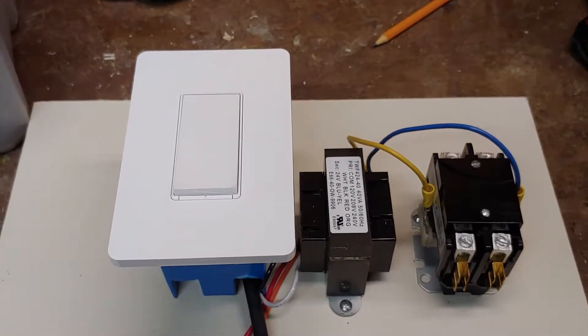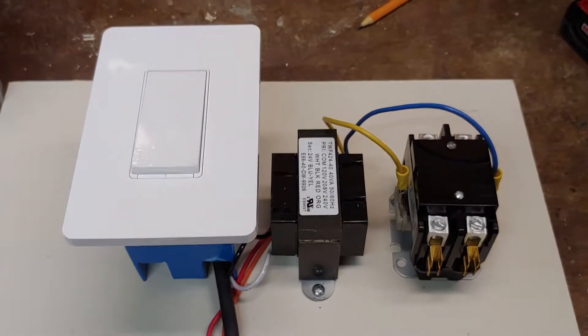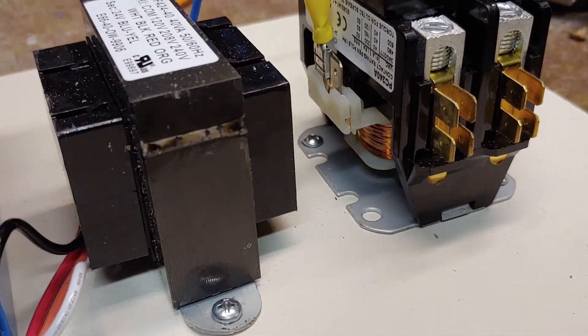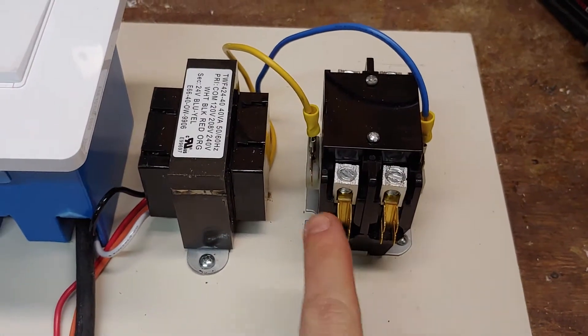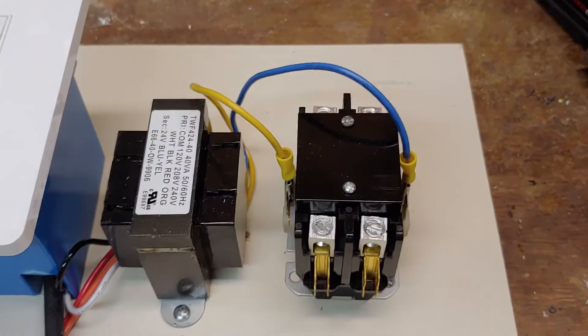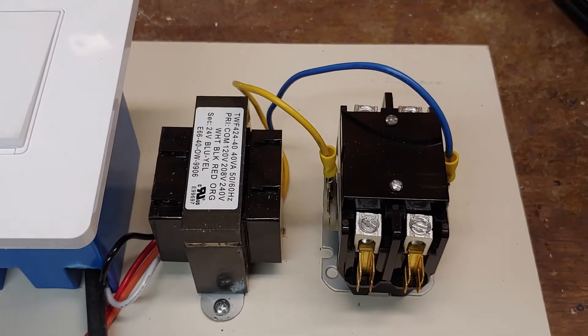So that you can control a high amperage or high load device, you can use a contactor. The contactor has a 24 volt solenoid in the bottom of it, and you can run 240 volts. You've got one hot, one hot, and it's switched to these two. You take the same hot over here, and it will switch them on and off. It's a nice relay, and it runs off a 24 volt transformer.